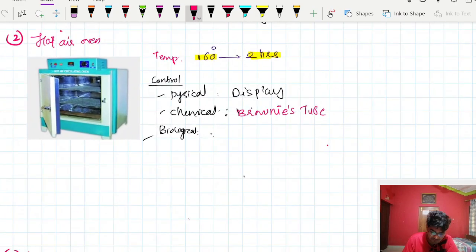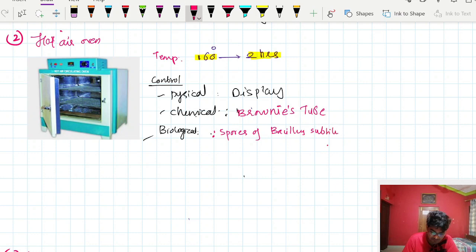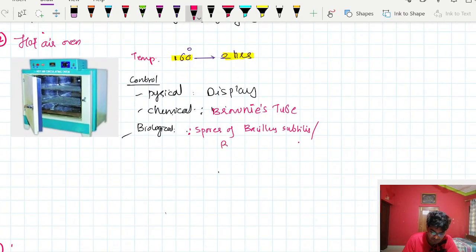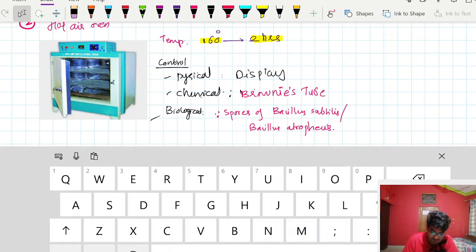Controls in hot air oven include physical display of temperature and time, the chemical control is Brownie's tube, and the biological control uses spores of Bacillus atrophaeus or Bacillus subtilis.